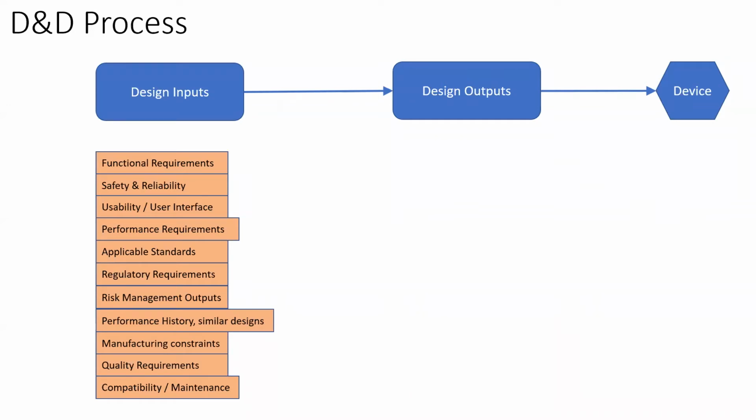Okay, so what is a risk management output? So we'll speak about risk analysis as we go along, but risk analysis is like the twin brother of design control, and the process of risk analysis is the process by which you as a startup or as an ideator would take the help of multiple stakeholders to define, in simple terms, what all could go wrong with this device throughout its life cycle, from the day I start design work till the day it is used in a patient or in any other setting, till the day it is eventually disposed of.